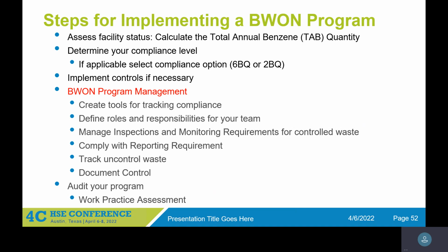I want to go real quickly through the inspection and monitoring requirements right here. For the tanks, you have to do initial and quarterly visual inspection, and you have to do initially and annually the non-detectable emissions, which is the LDAR. Everybody knows what Method 21 is, right? For the internal floating roof tank, you basically have to follow NSPS Kb, where you have to empty and degas every 5 years.